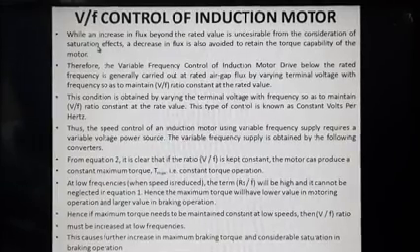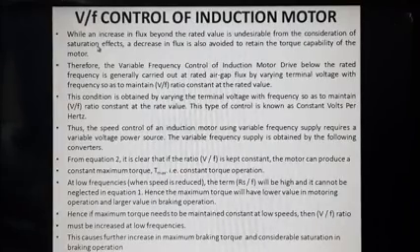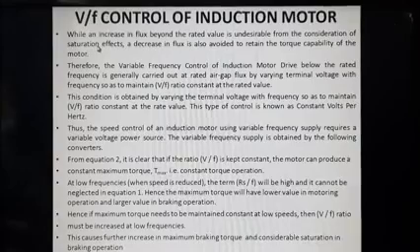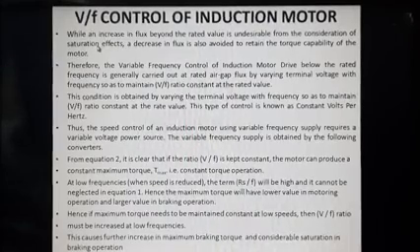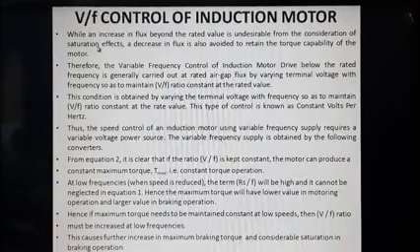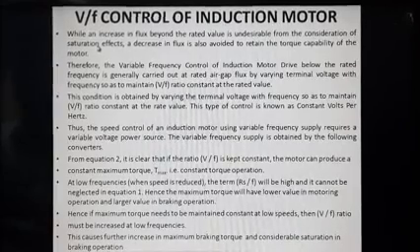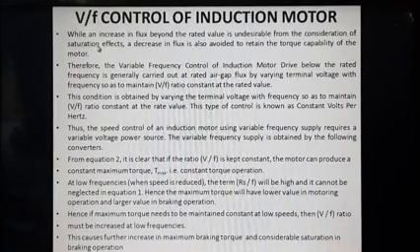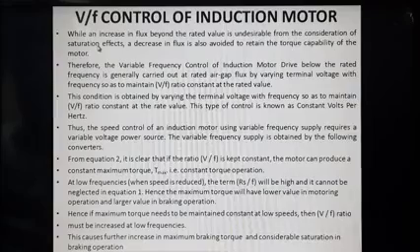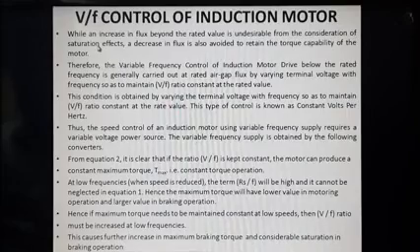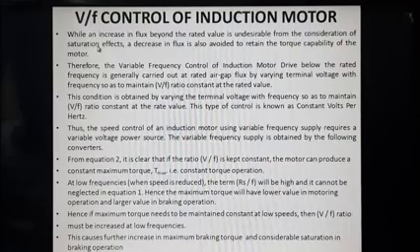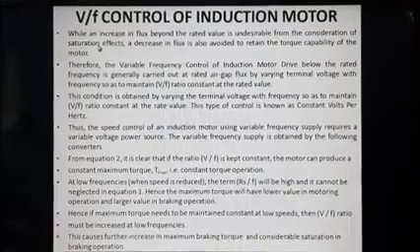In effect, I can say by simply varying the frequency alone, either to increase the speed or to decrease the speed, we will not be getting the desirable effects. If you are trying to decrease the speed by reducing the frequency, definitely the operating point is shifting from the knee point to the saturation region. Similarly, if you are trying to increase the frequency, the maximum torque capability of the induction motor is getting reduced. So to get rid of these problems, by varying frequency alone we are not able to achieve the desired operations. We will be using a new control technique.